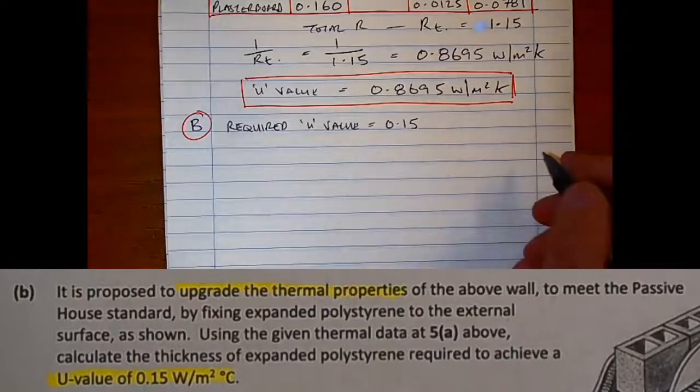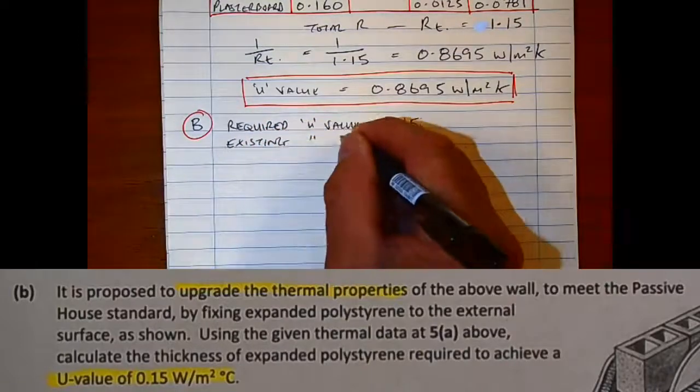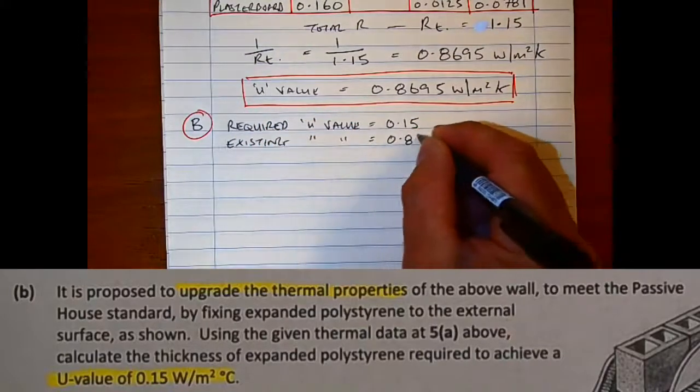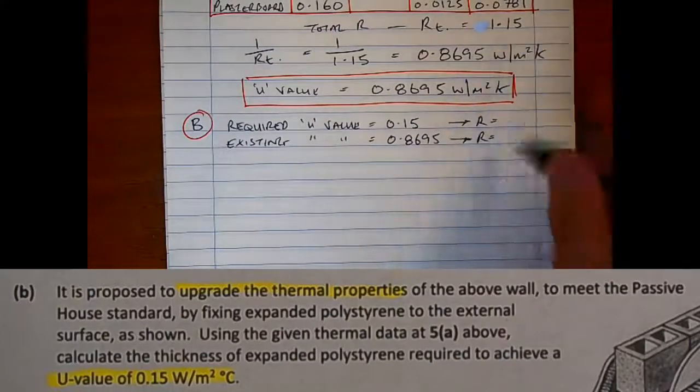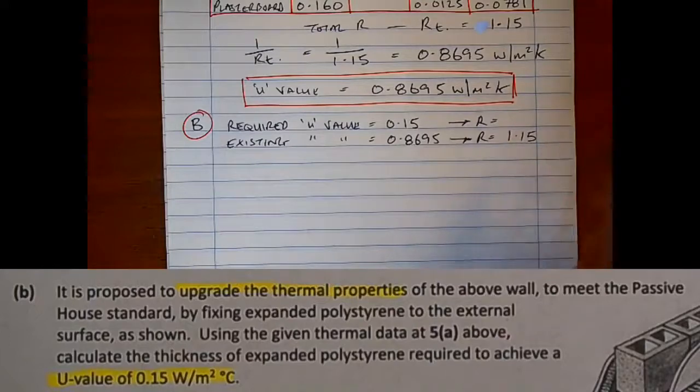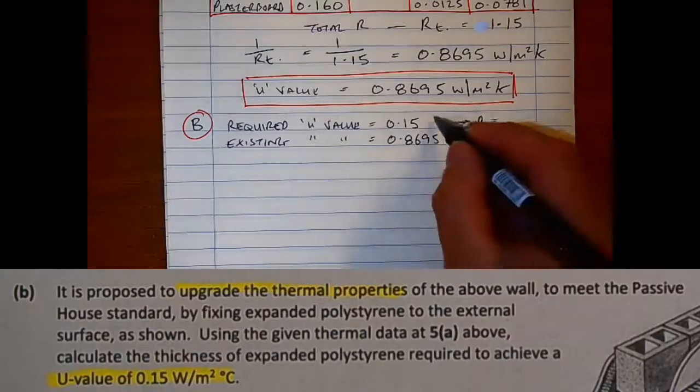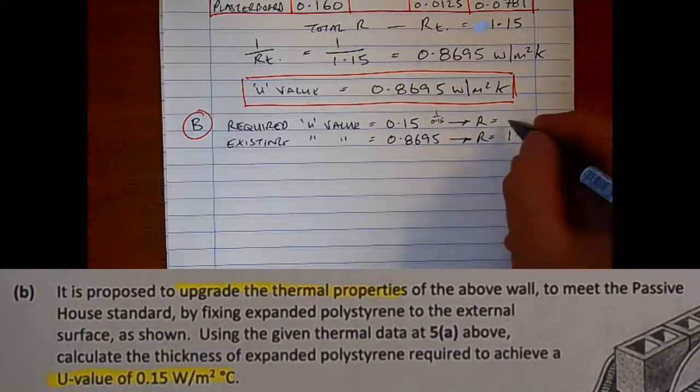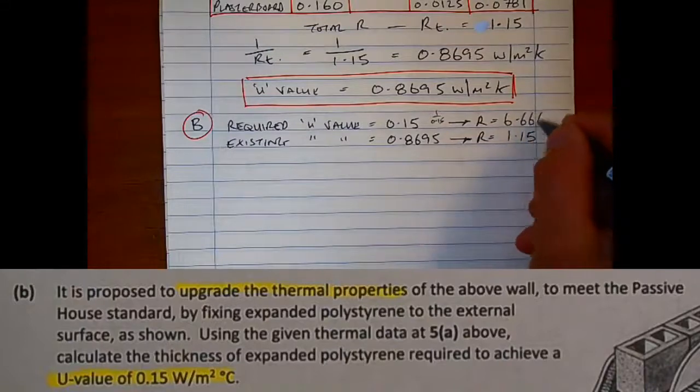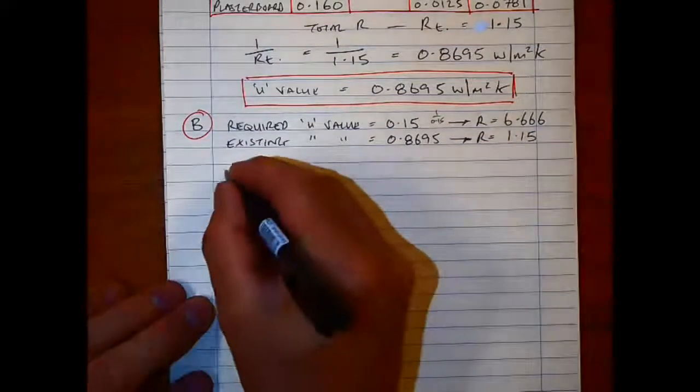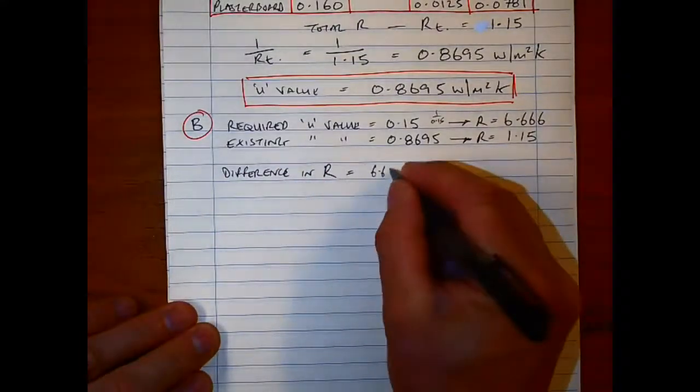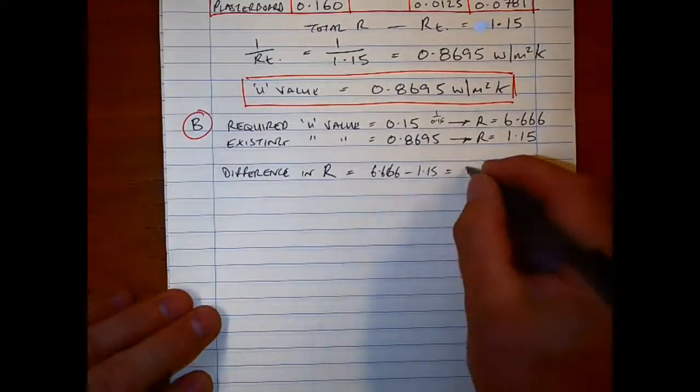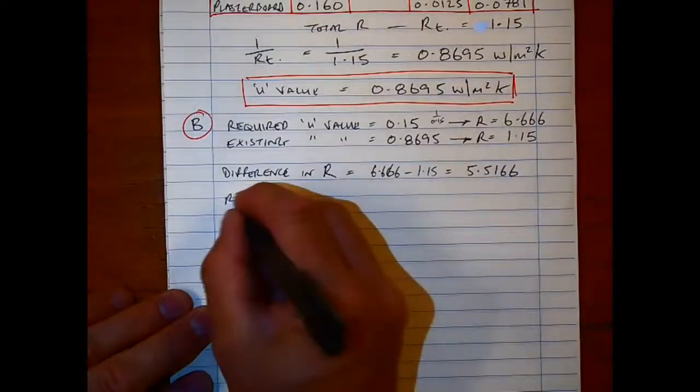For the B part of the question, we were given a new U-value. It's proposed to upgrade the wall, and you can see it here, by adding on insulation. All I'm writing down is the two U-values: the one that we calculated, and then the one that we're actually looking to achieve. We can go back a step to the resistivity or the resistance, and we have it from the table before. To work out what the resistance is for 0.15, just put 1 over it, and it gives us 6.666.